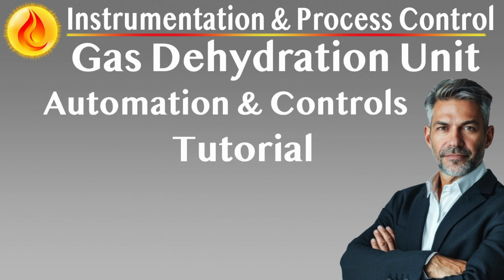Accessible instrument locations. All devices are mounted outside hot zones, within reach from walkways or maintenance platforms. Vibration-affected instruments are isolated or supported with vibration-damping mounts. Summary. Instrumentation on the Glycol Contactor combines precise process monitoring with robust safety control. From gas flow regulation and lean glycol feed optimization to rich glycol level control and foam management, each loop is designed to uphold dehydration performance while protecting equipment and ensuring environmental compliance.